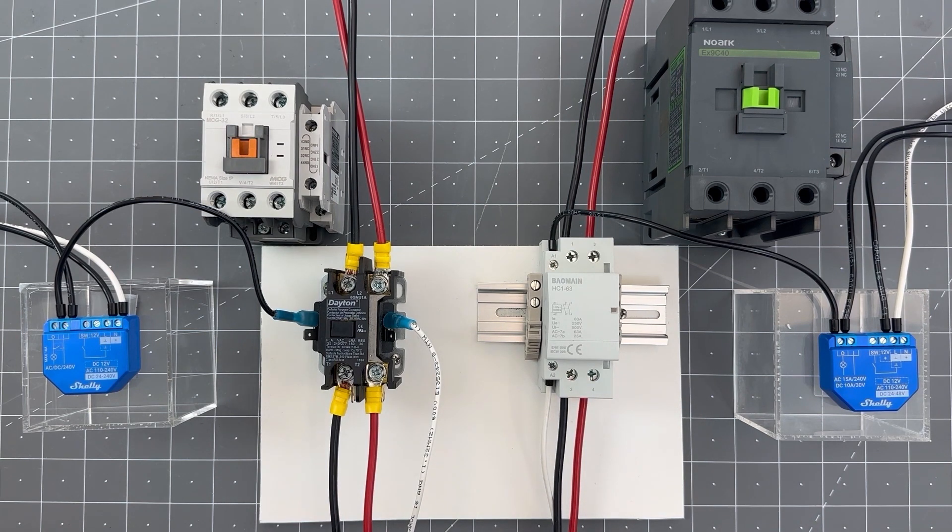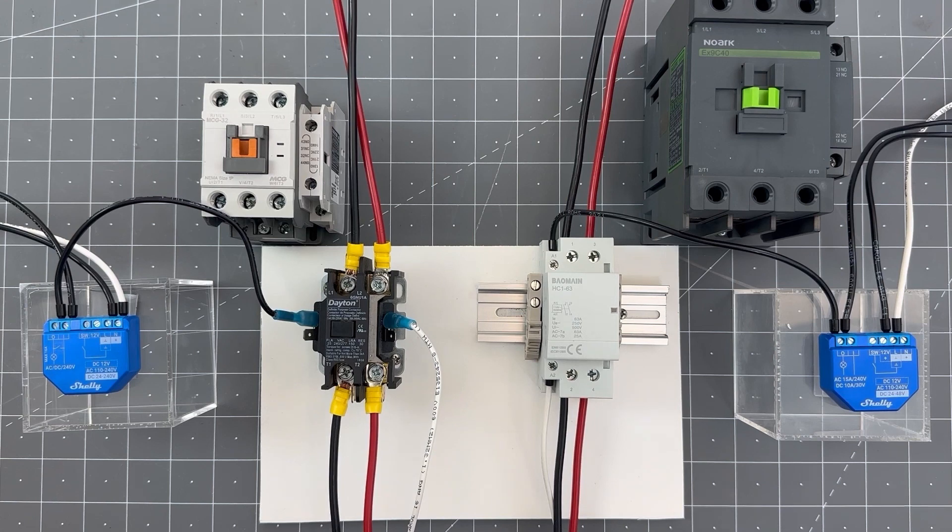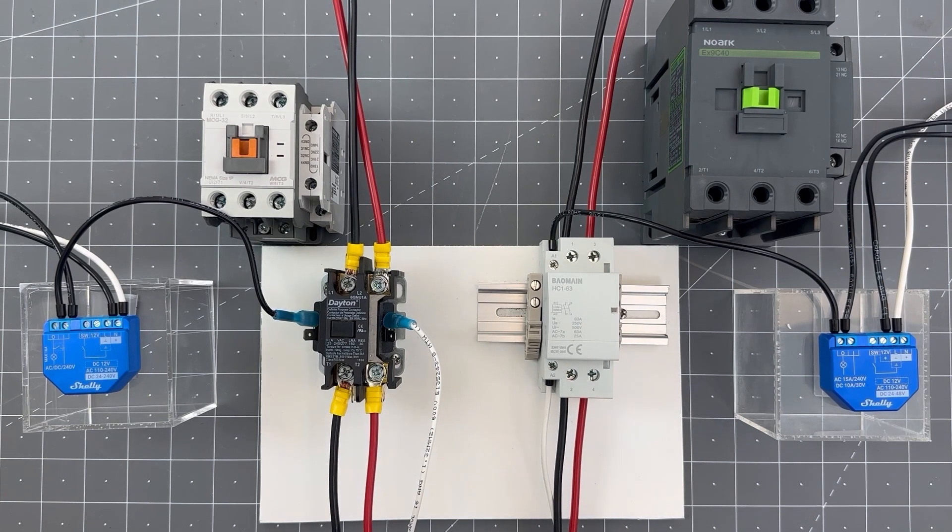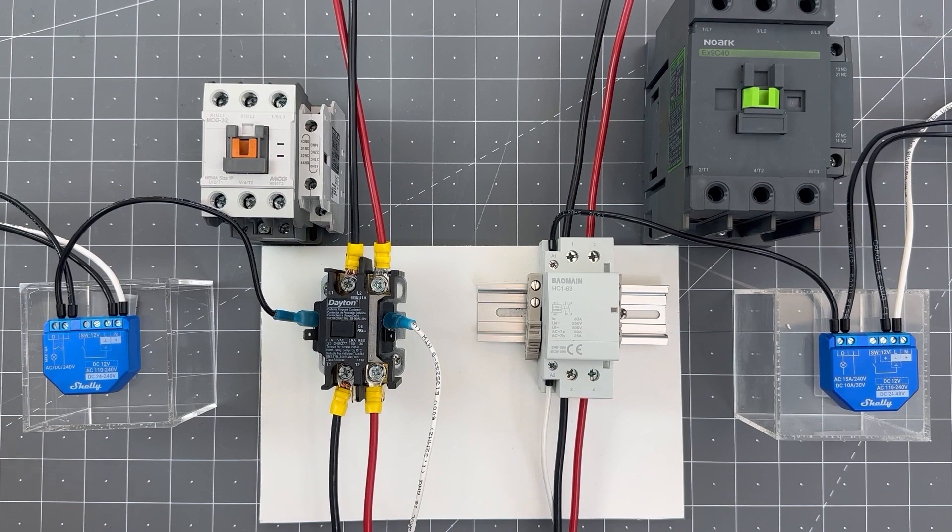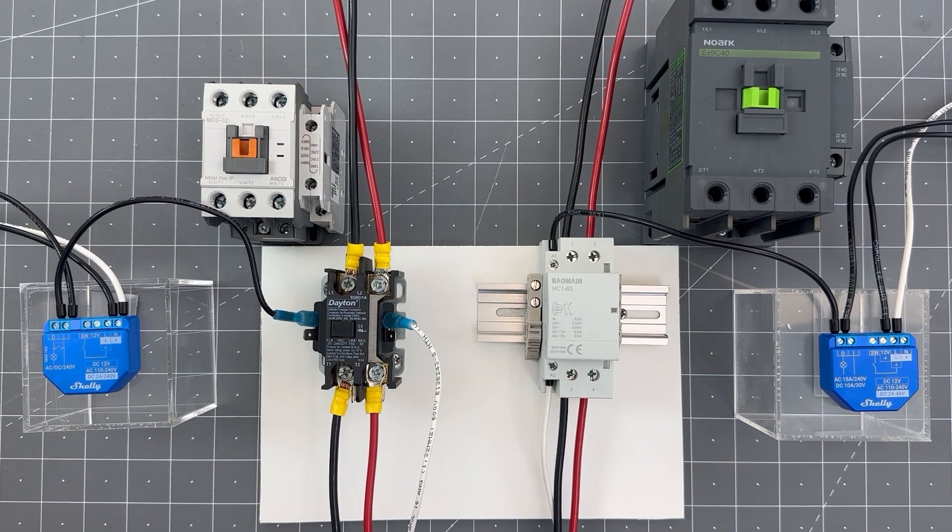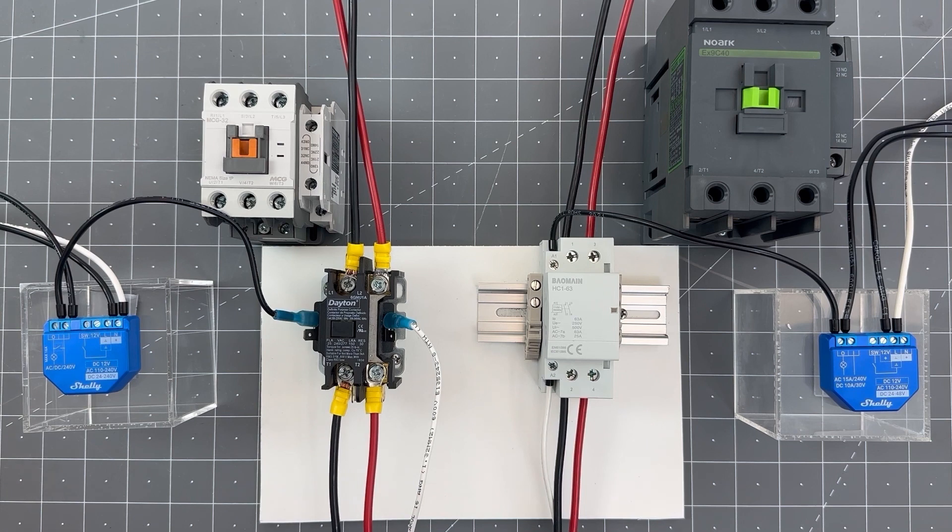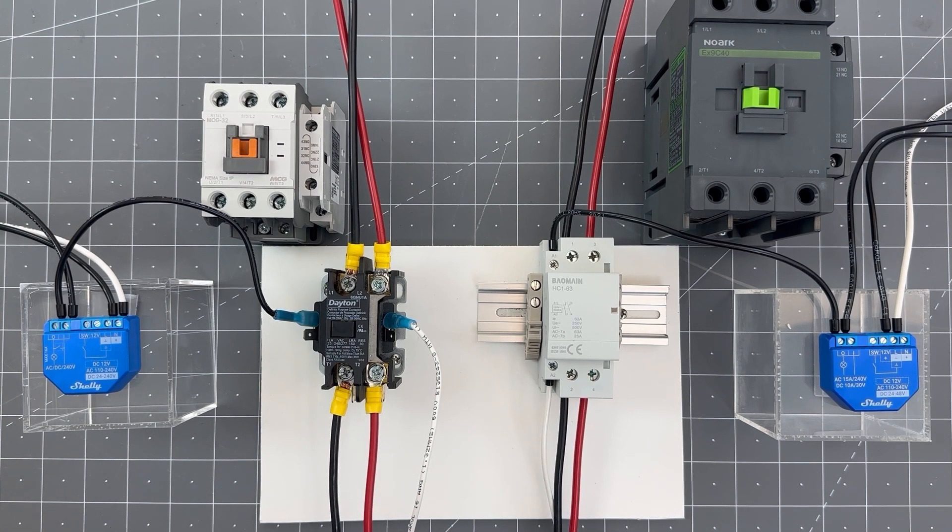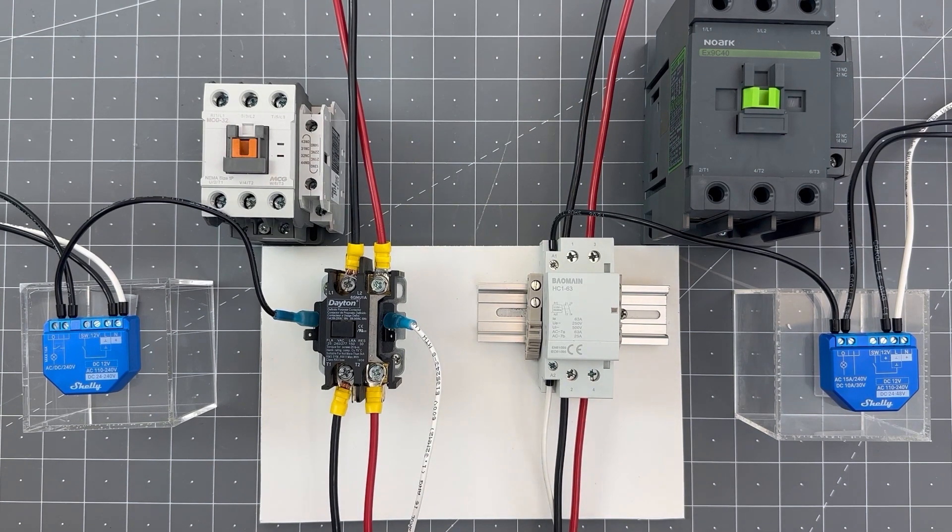Now, if you look at the labels on the contactor examples we have here, you'll notice that there are a couple of different ways to designate the terminals. The air conditioner contactor on the left has L1 and L2 for the incoming line from the breaker panel. Then you see T1 and T2. Those are the load going out to the device you're controlling. You have a black wire coming in that's connected to terminal A1 and is triggered by the Shelley relays out. The A2 terminal is connected to a neutral wire.